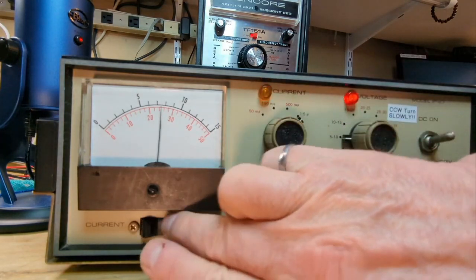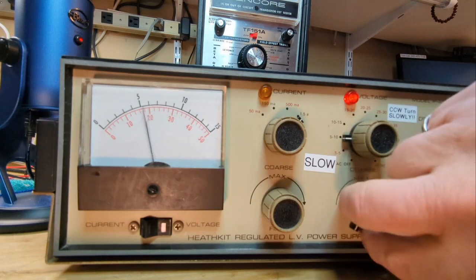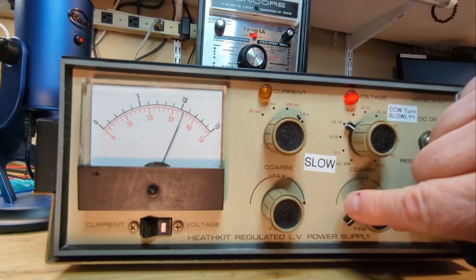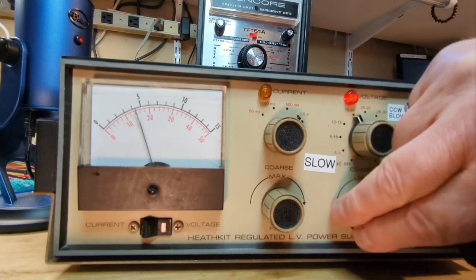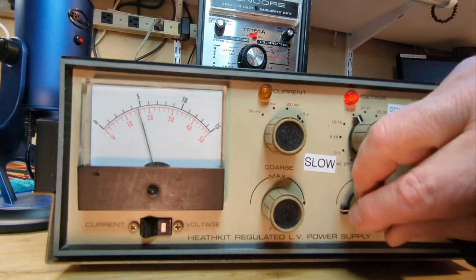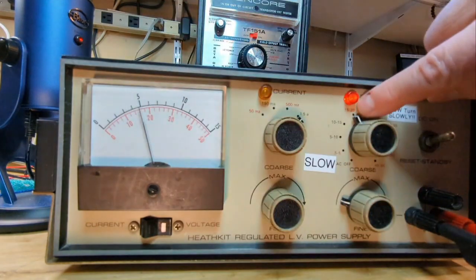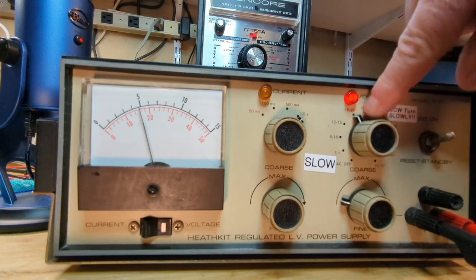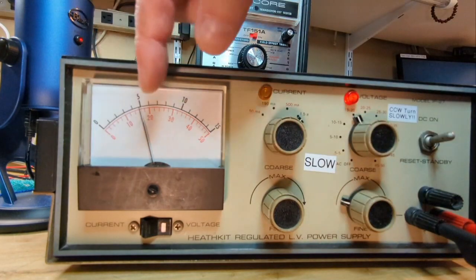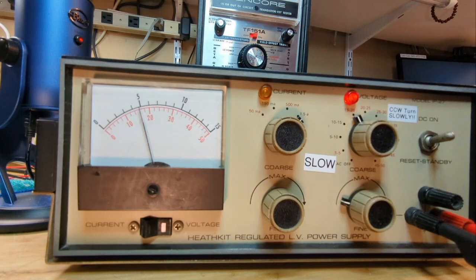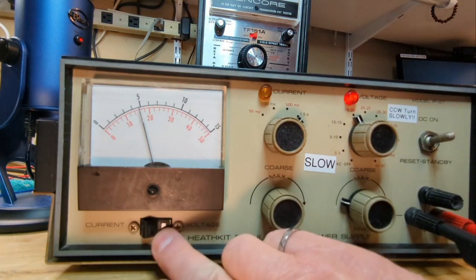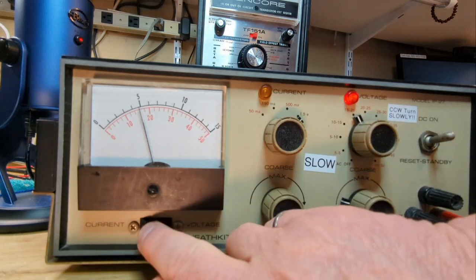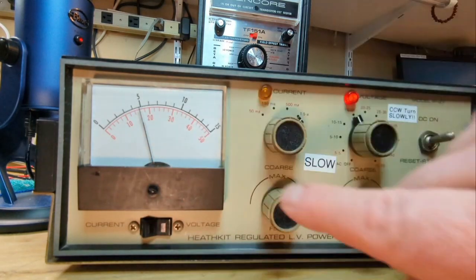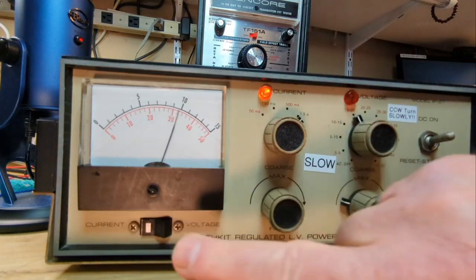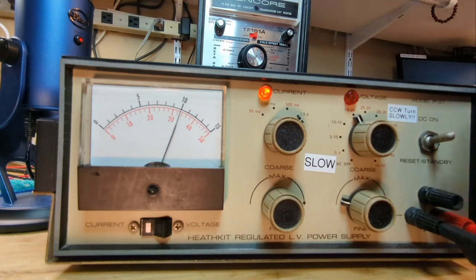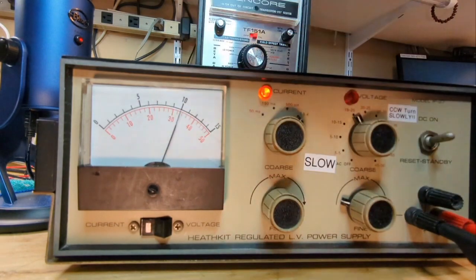If I raise it to 16 volts, then you would expect the current to go to 1 amp. 10 to 15, 15 to 20, and that is 16 volts is right there. That's the red scales. You have to mind your red scale, black scale, all that nonsense. So 16 volts on the 10 to 20 is right where you show. 3 divisions past the 10. I'm going to flick it on the current range, and we should go to 1 ampere. Bang, right on, 1 amp. 15 to 20 range, 1 ampere exactly.